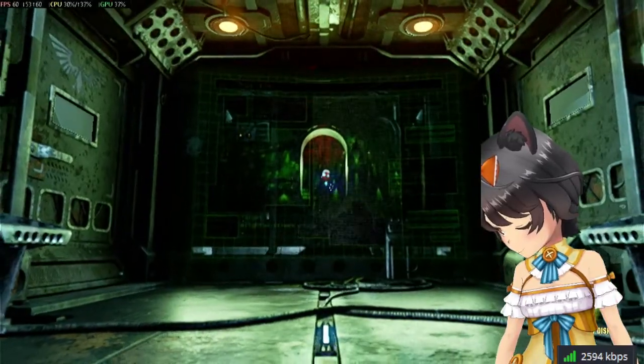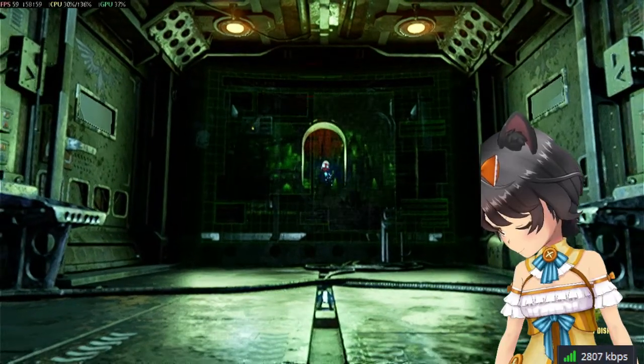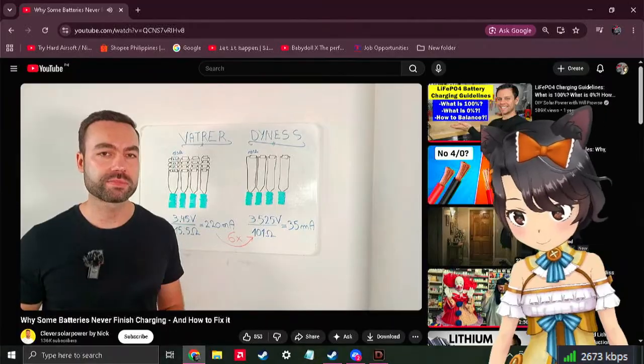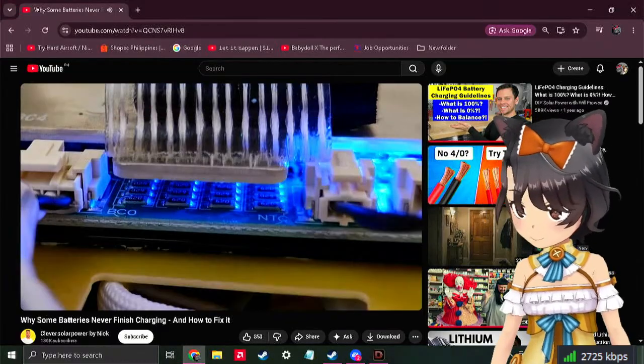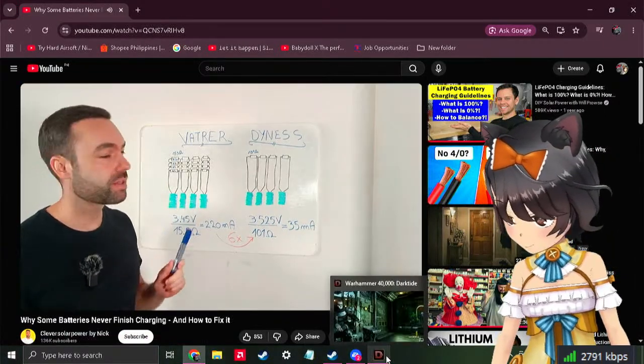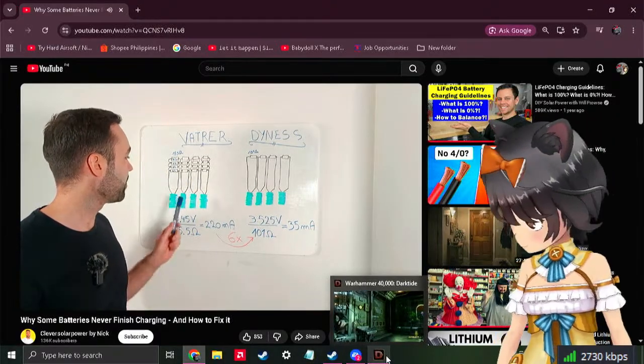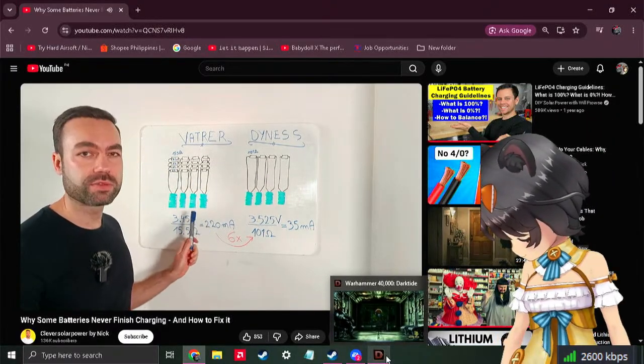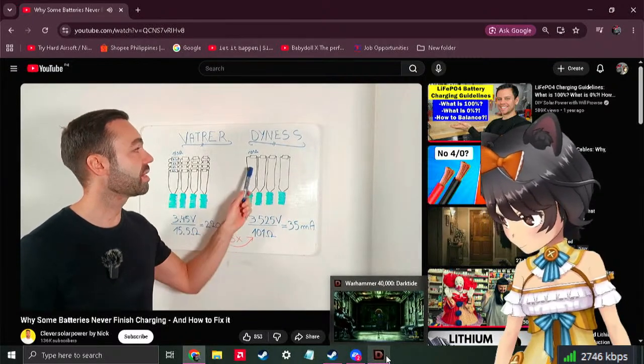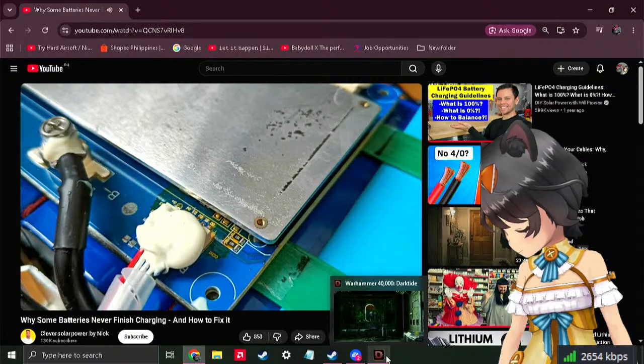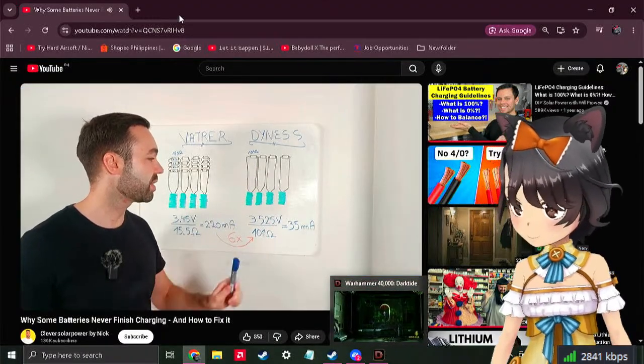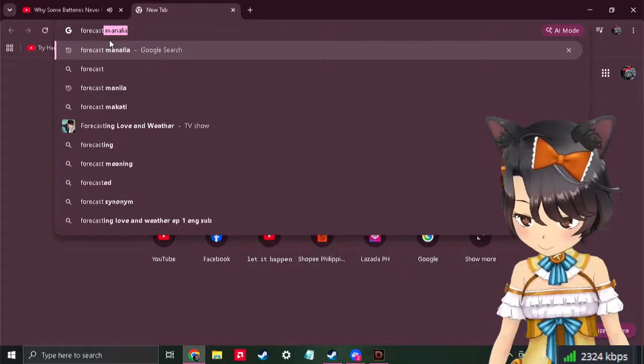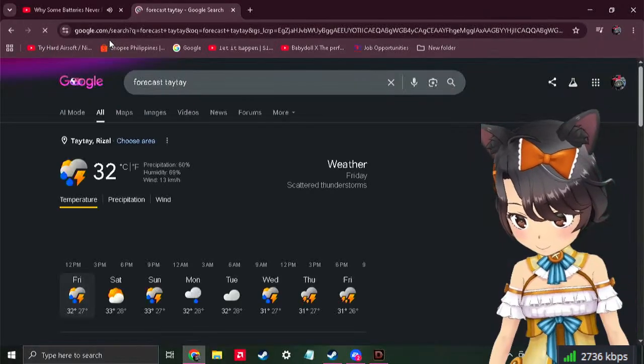Both batteries use passive balancing. The BMS bleeds the high cells through resistors, which creates heat. On the Vatrer BMS, there are 4 resistors in parallel, each 62 ohms, making an equivalent of 15.5 ohms. Calculating this gives a balancing current of 220 milliamps. The Dyness only has a 101 ohm resistor per cell, and calculating that balancing current at the starting voltage gives 35 milliamps, and the datasheet confirms this. So the Watt has roughly 6 times the balancing current of the Dyness.